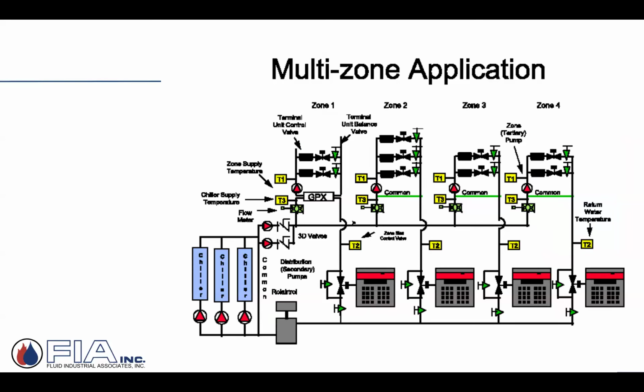Going from that type of drawing to perhaps what might look like fairly confusing, but this might be referred to as a primary, secondary, tertiary application, where I might have, in this case, primary or production pumps from my chiller plant. I might have distribution pumps that are secondary pumps that are feeding. In this case, these zones might be buildings, might be dormitories, might be classrooms, might be wings of a hospital. And then within each building, they'll have their tertiary, their third pump, their own pump that's sized specifically for the flow load of the terminal units within that building. So again, that's a design principle that happens quite frequently as well in the industry. So whether it's a simple little variable primary to primary, secondary, tertiary.